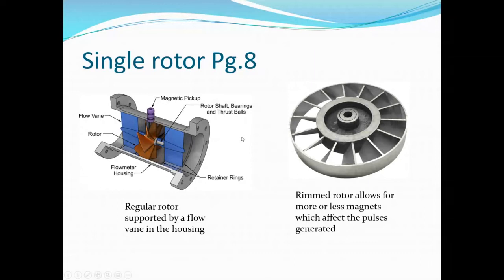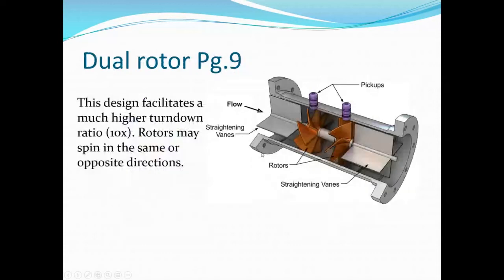The second rotor type is the dual rotor. The big benefit of the dual rotor is a much higher turndown ratio — a much wider operating range with maintained accuracy. Because these meters can be bidirectional, the rotors may spin in opposite directions depending on which way the flow goes, and may have opposing angles on the fins.